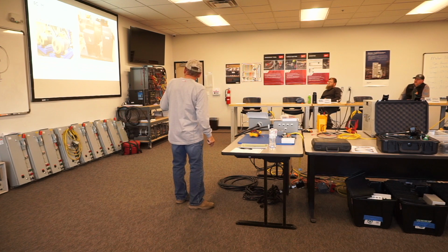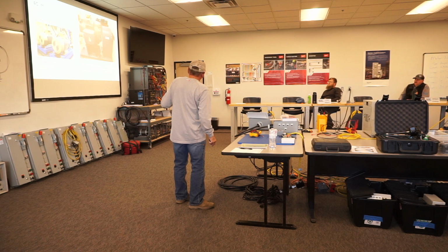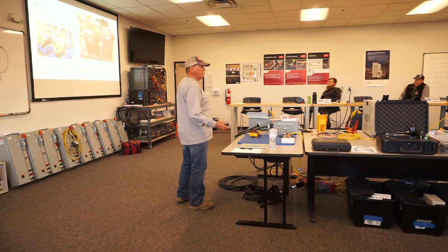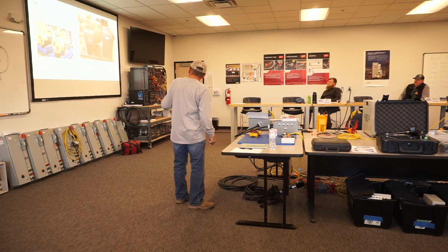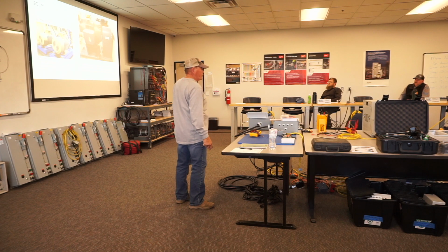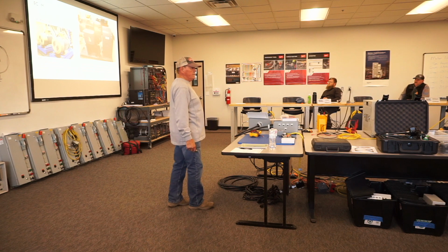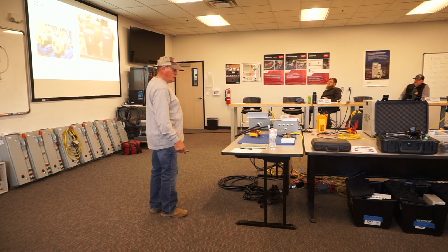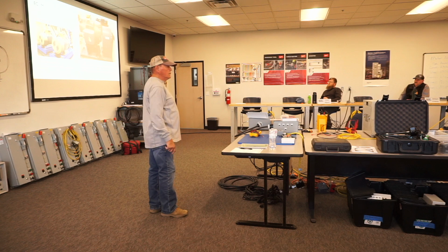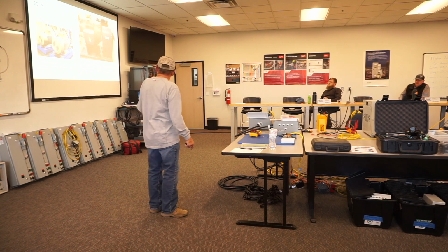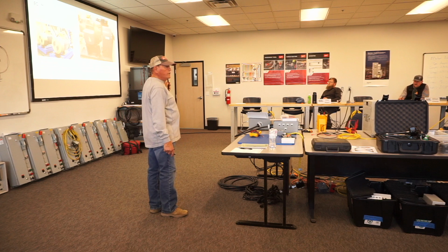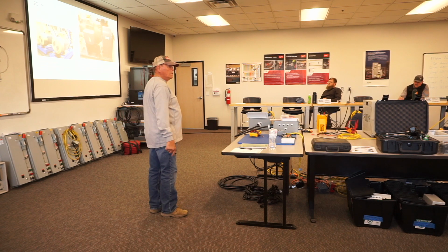That shaft is connected to a grounded surface. And if I'm generating all this high frequency up here in this part, I'm going to go through that bearing into the shaft because that's my path to ground. But if I provide this, now there's my low impedance path to ground, only if that pad is grounded properly, effectively. Now, I fixed that problem. I don't have to change bearings no more. I don't have to put that Band-Aid brush on there. There's a fix.